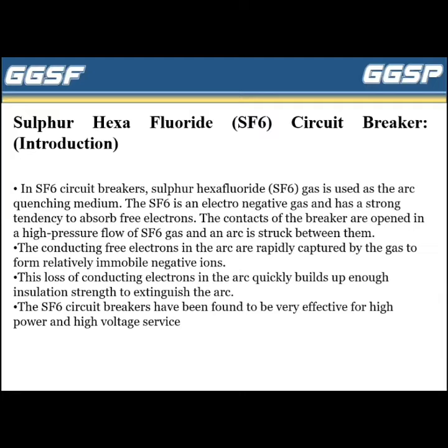Sulfur hexafluoride circuit breaker introduction. In SF6 circuit breakers, sulfur hexafluoride gas is used as the arc quenching medium. The SF6 is an electronegative gas and has a strong tendency to absorb free electrons.